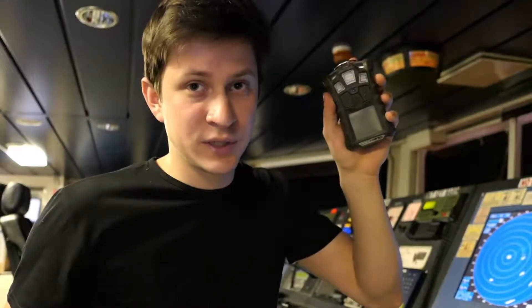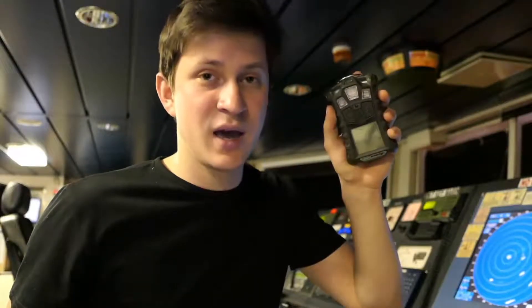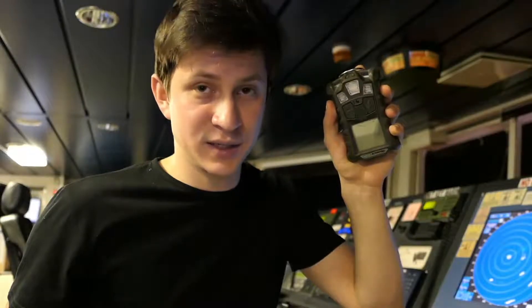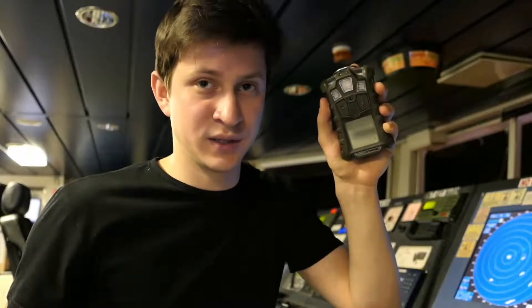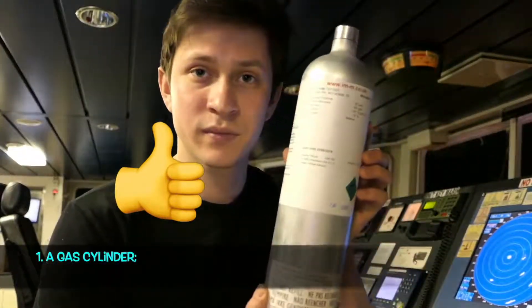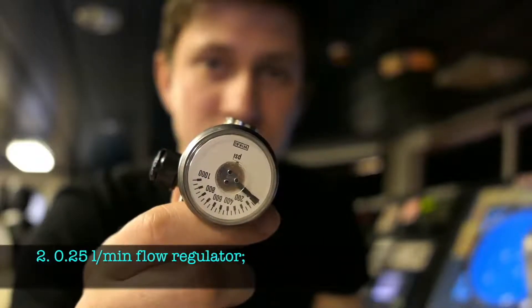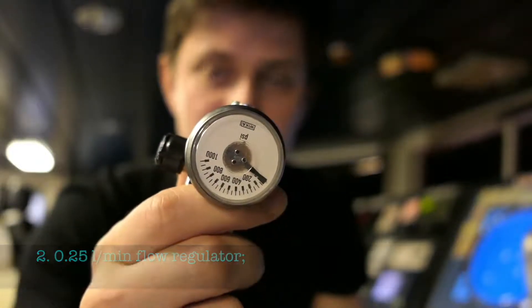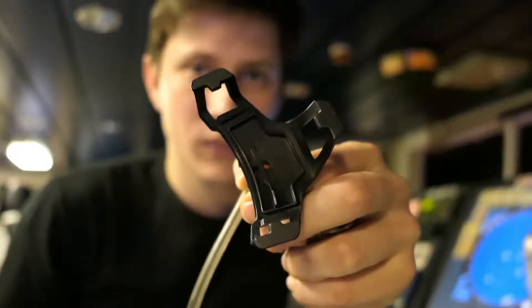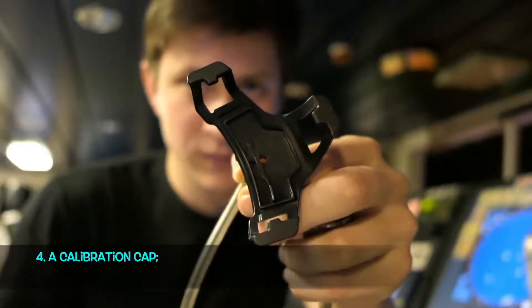The Altair 4X multi-gas detector can be equipped to detect combustible atmosphere, oxygen-deficient or oxygen-rich atmosphere, and toxic gases for which a specific gas sensor is installed. A standard set will include a gas cylinder, a 0.25 liters per minute flow regulator, gas tubing, and a calibration cap. To switch on the device, press the ON-OFF button briefly.